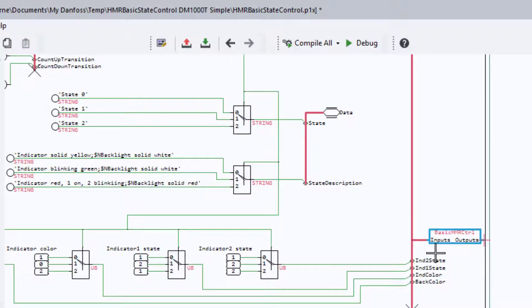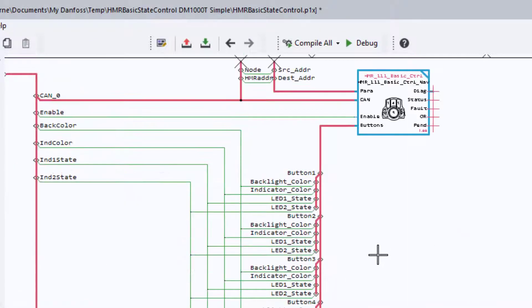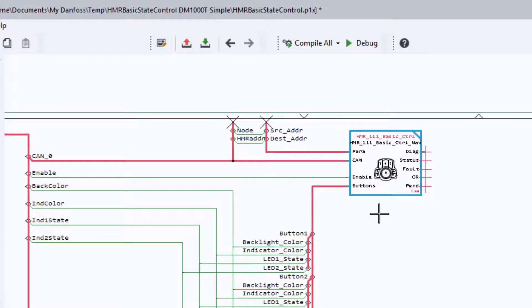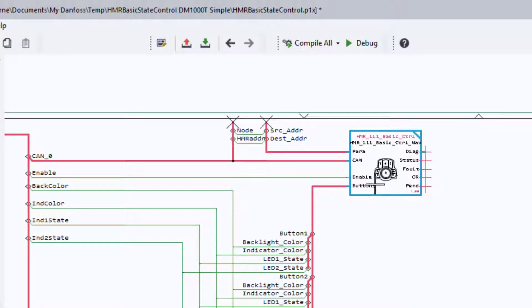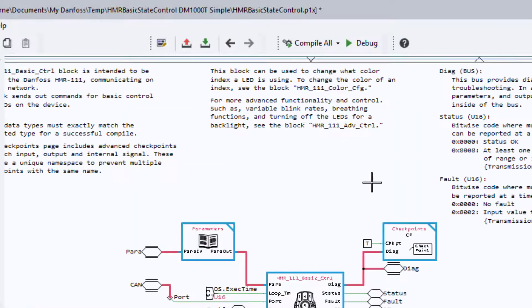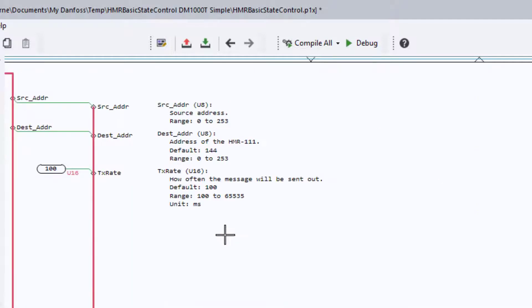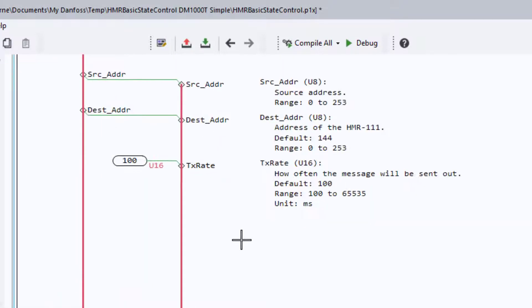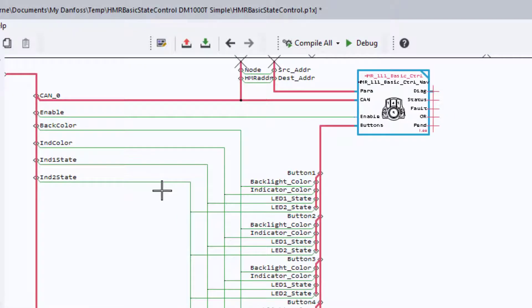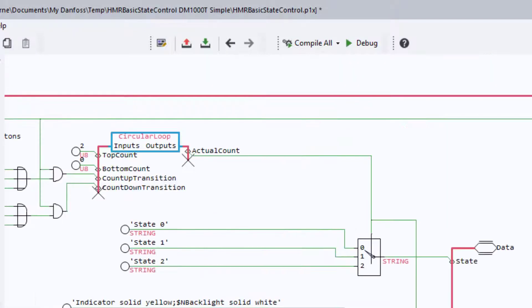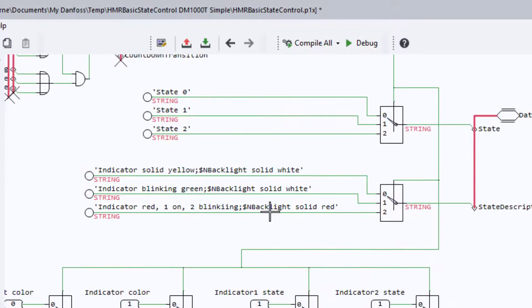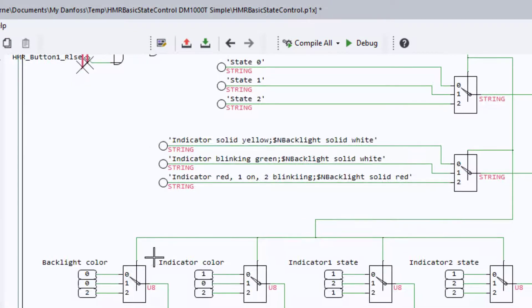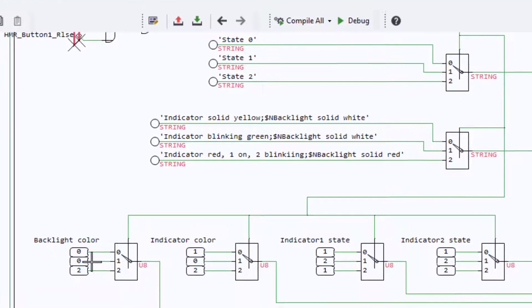So that gets passed to our basic control block. And like I said, that's all we have to do is pass the values to the block. The actual sending of the message is done automatically on the schedule here. By default, it's done at 100 milliseconds. So that's all the programming that has to be done for the first state.